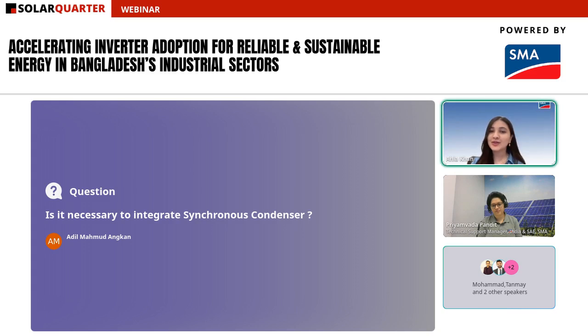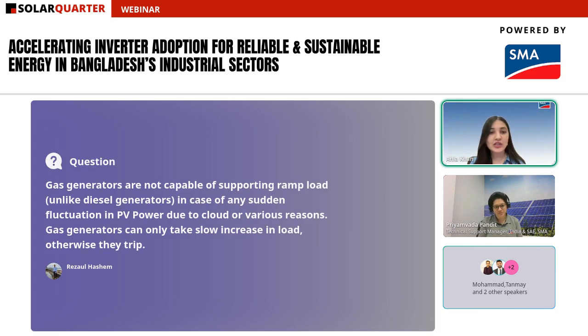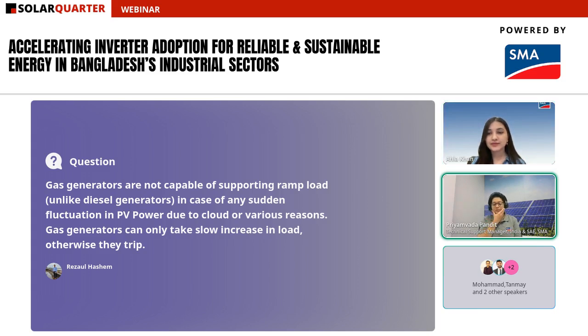Another question for you: gas generators aren't capable of supporting ramp load, so in case of sudden fluctuation in PV power due to clouds or other reasons, gas generators can only take a slow increase in load, otherwise they trip. Is there any solution? Typically, if you have this problem, we would include a battery system - not necessarily to supply the load itself, but to support the ramp rate control you'd require in that case.